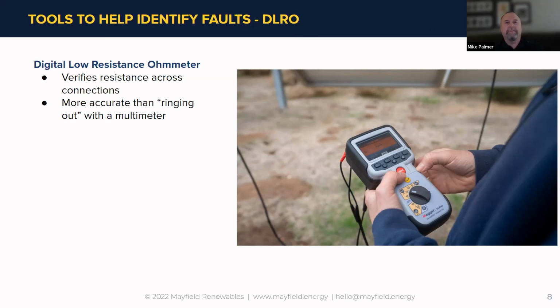And I know that's not the picture we showed. We could have showed bus bars. And I travel with the bus bar using the DLROs to show the difference of one that's lugged down tight on torquing and one that isn't, and what happens. And the big thing that happens if we don't make sure that connection is firm is heat builds up. And what's bad about the heat building up? It ruins things. So the specs are lagging with what we need to do on O&M to shore this up.